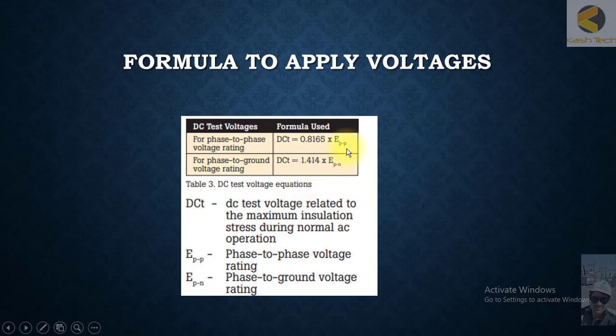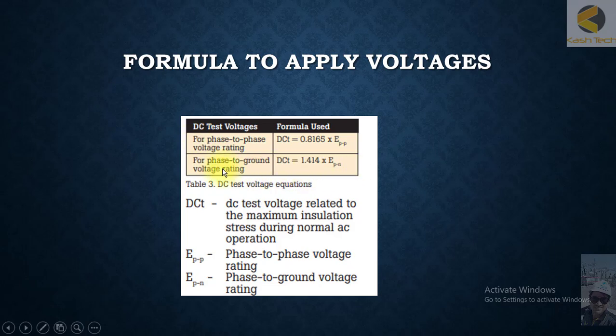For phase-to-phase ratings, you apply the rated voltage multiplied by a coefficient of 0.8165 to get the DC test voltage. There is also a corresponding formula for phase-to-ground ratings.